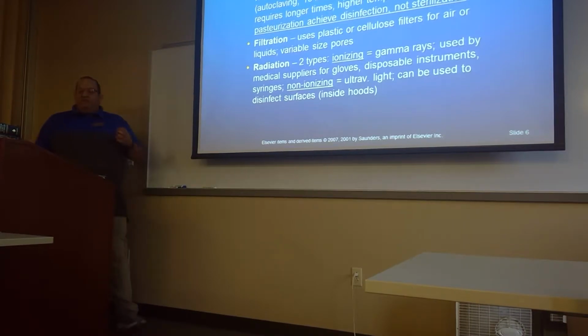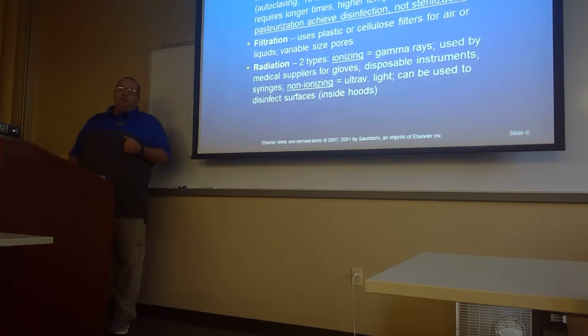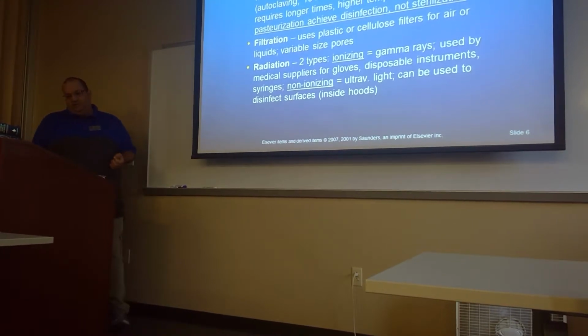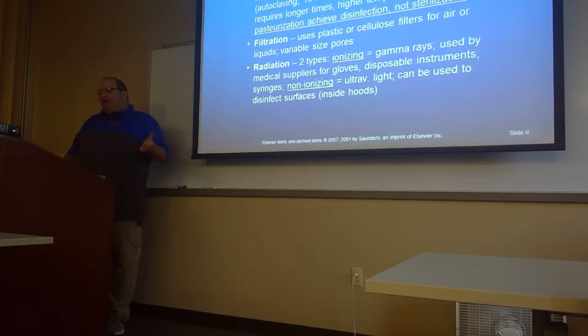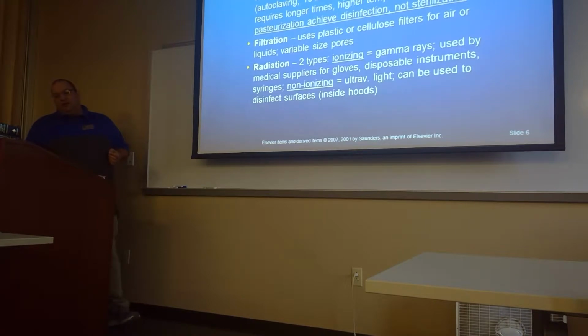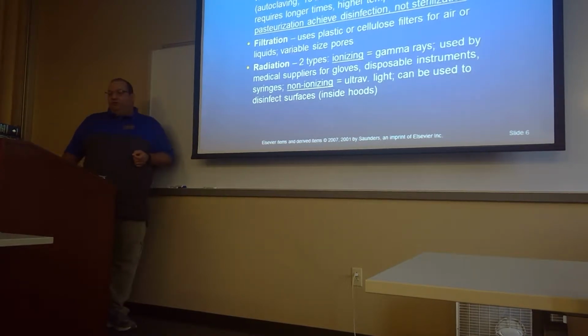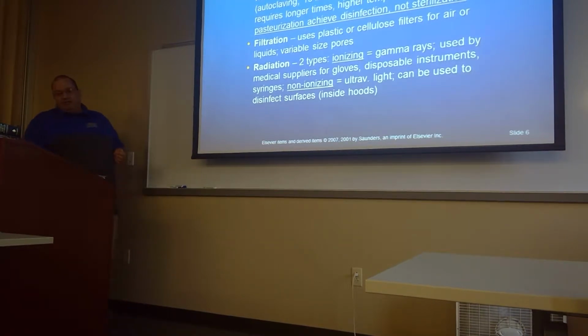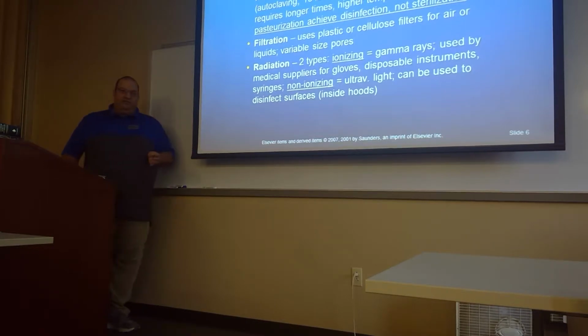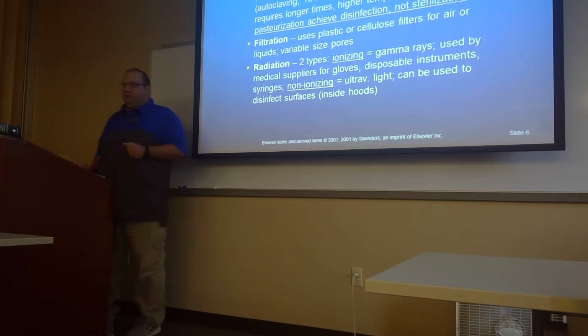An autoclave is moist heat. That is a pressure bath using steam to disinfect. Dry heat requires longer times and higher temperatures. Boiling and pasteurization do not achieve sterilization. It disinfects.